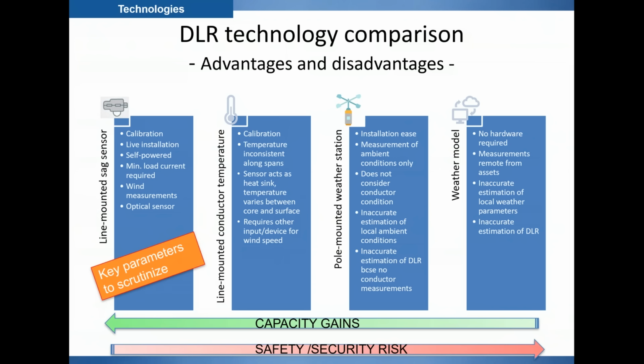Next option, which is more accurate, would be to have sensors mounted on the conductor itself, typically a temperature sensor that would measure the temperature on the conductor. That would give you the same benefit as the previous ones, with the addition of having at least one parameter known on the behavior of the conductor, namely the temperature, but you would still be blind as to the wind speed and other parameters. And also what we've seen and what the research has shown is that the temperature of a conductor is very difficult to determine, because at best you would determine a point measurement on a very precise location of one span. We have seen that the variations of temperature from span to span and even within the span can be actually quite large. So therefore you would have to be cautious with that, and prudent operators would typically downgrade that information in order to calculate the rating.